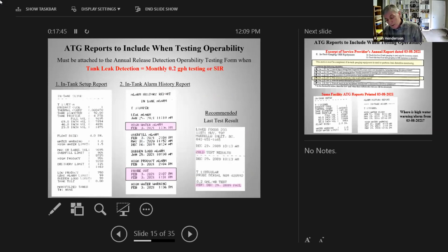Okay, and so I guess the heart of the matter relative to testing the tank gauge and probe is you need to be able to document that yes, you in fact did pull the probe from the tank. You did in fact verify that the floats were reading correctly. And the way that you can do that is kind of limited, but we do the best that we can. And so one of the things we're going to do is include these reports from the Veeder-Root itself. We're going to print these reports if possible, and we're going to make these part of the report.